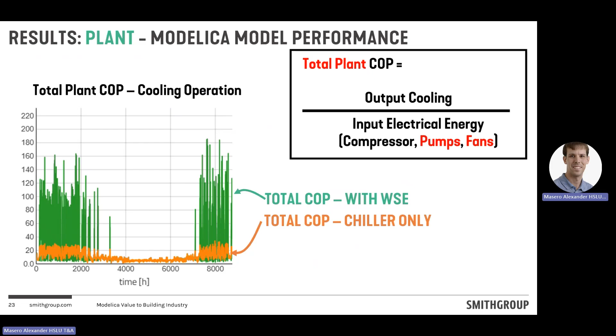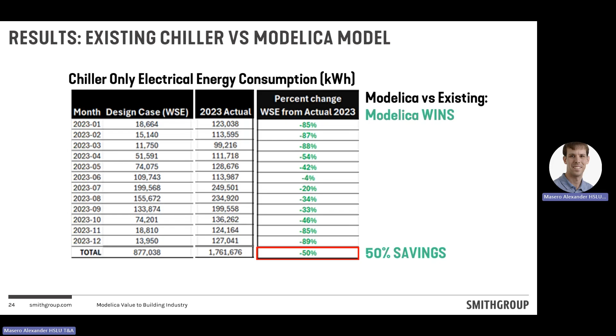So very good performance, able to capture and compare two strategies. We also had actual chiller data, so we isolated the chiller compressor from the Modelica simulation and compared it to what they actually ran. We expected savings, and we got about 50% against that. It was an old plant, there's probably controls issues and all this stuff, but the owner really liked to see this as a progress update.